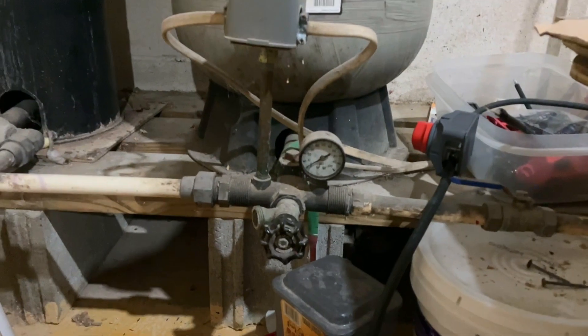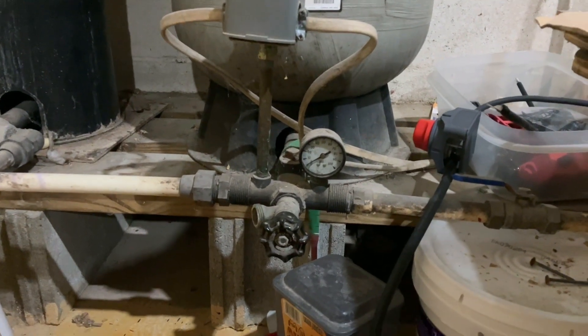I don't want to just leave it there. I want to look at running the well with a few larger loads just to see how it's going to perform. So I turned off the well circuit breaker, went through the house, flushed all the toilets multiple times, ran the sink a little bit just to get that pressure down, and we are back down to zero on the pressure tank. I'm going to run a microwave and then add in a vacuum cleaner — two fairly high loads — and see how everything runs together.